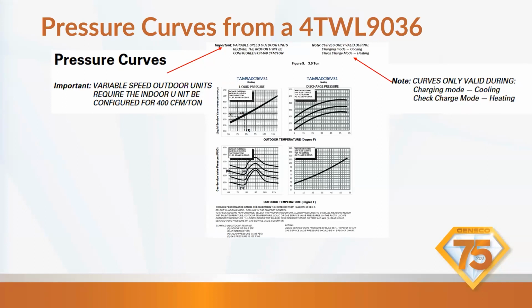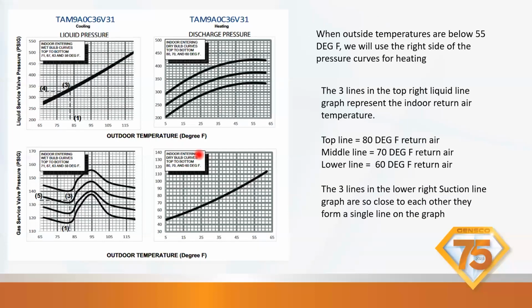So with these pressure curves, you have cooling on the left side, which in cooling mode, we're going to try to achieve our 10-degree subcool, but we can also see what our pressures should be. And then we have heating on our right-hand side. So we're going in the heating season. We're going to be using our heating pressure curves on the right-hand side. Okay, here's a closer view of it. When outside temperatures are below 55 degrees, we'll use the right side of the pressure curves, right? So heating, we want to be on the right-hand side.